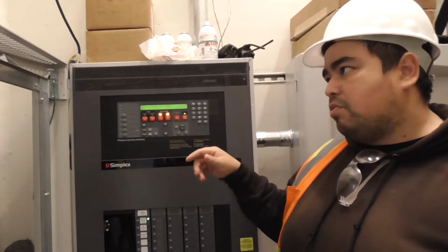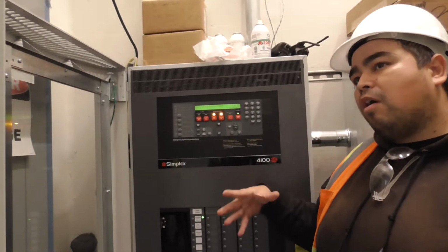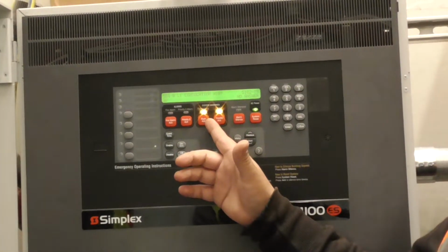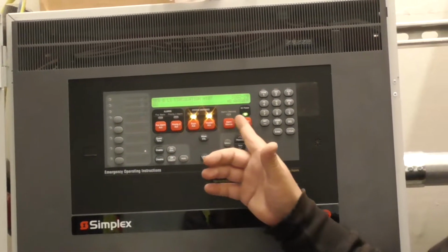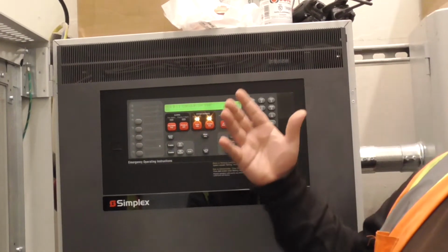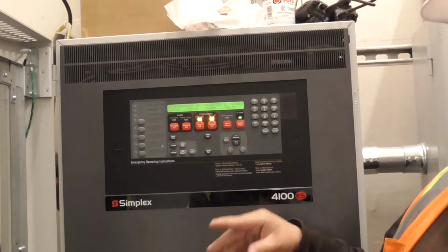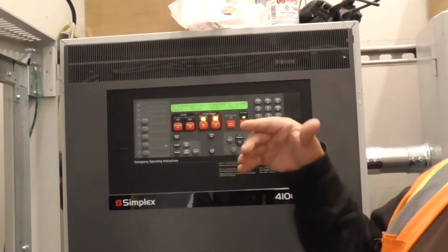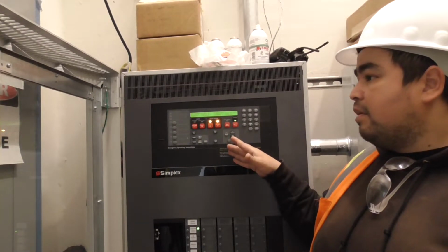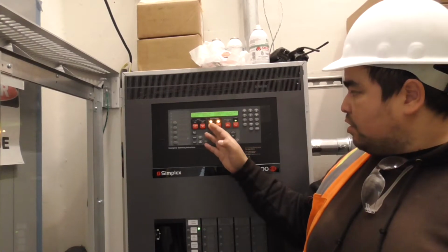When the smoke detectors go into alarm, they don't actually set the whole building into alarm. They set their own apartment into alarm, and they'll continue to be in alarm until somebody comes, acknowledges the supervisory, resets the system. So you can either hit reset and it resets, or you can silence. It'll silence and then you can hit reset. You can do either one. But it's not going to fully reset until you hit system reset. So after you acknowledge the supervisory, even if you silence, you always want to reset. Otherwise their apartment is going to keep going off and going off. So that's a supervisory event.